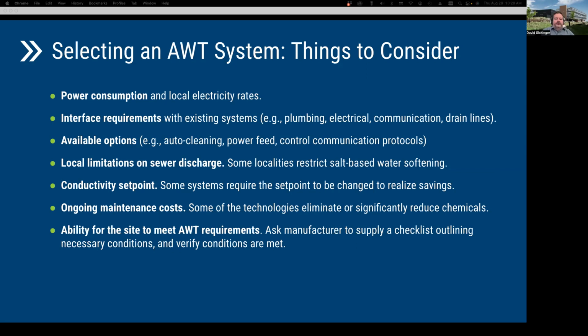Then you also want to consider system attributes such as flow rate, measured in gallons per minute, pressure, and predetermined water conductivity set points. At some sites, we did find that with existing operation, there was something they did not want to change, which was a conductivity set point for a blowdown. And then the ability for the site to meet AWT requirements, so analyzing the system. GSA staff recommends that the manufacturer supply a checklist outlining the necessary system conditions, and then the design team should verify whether the existing conditions align with those requirements.